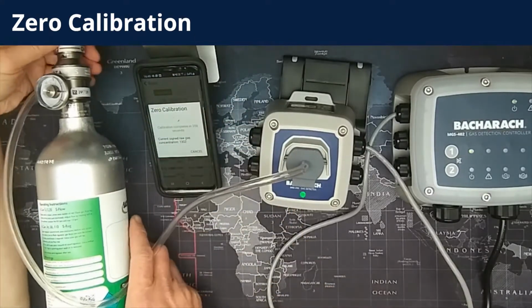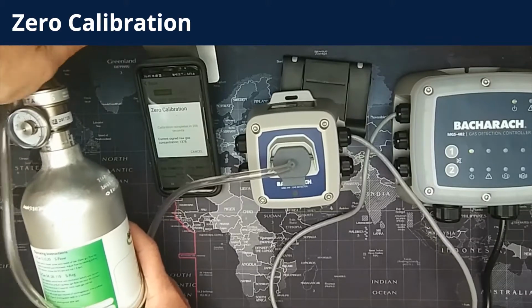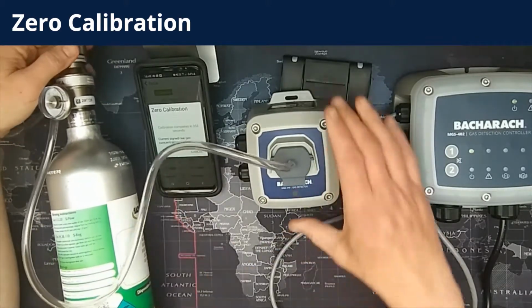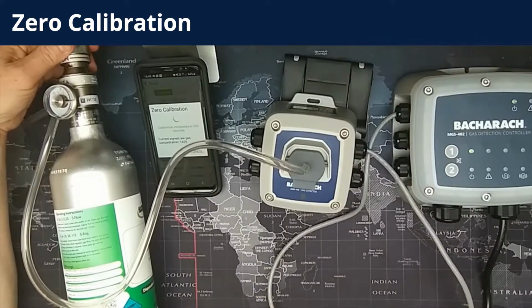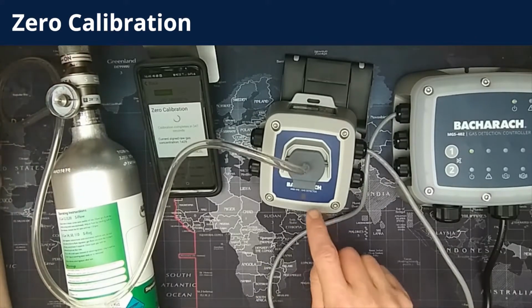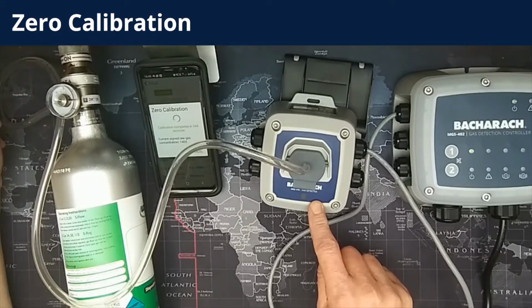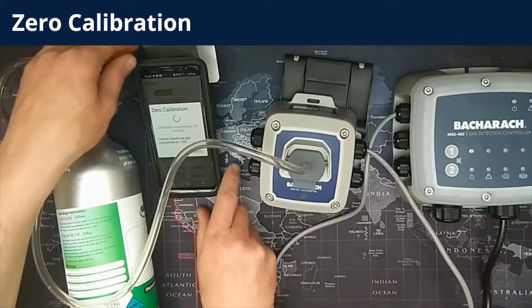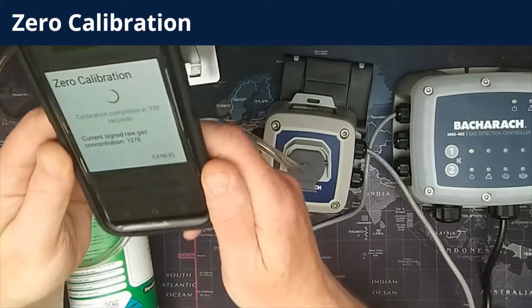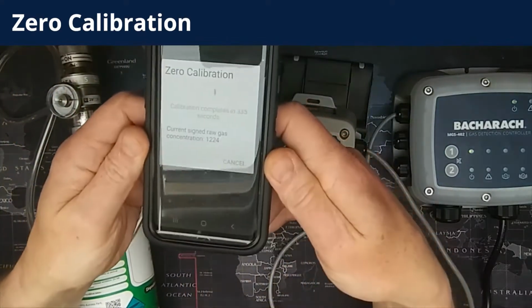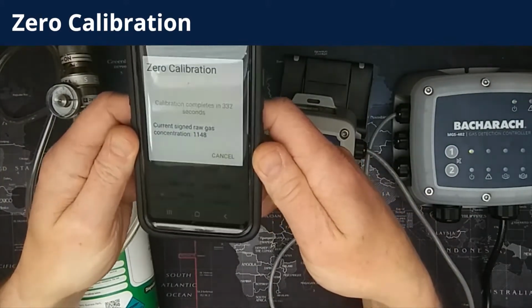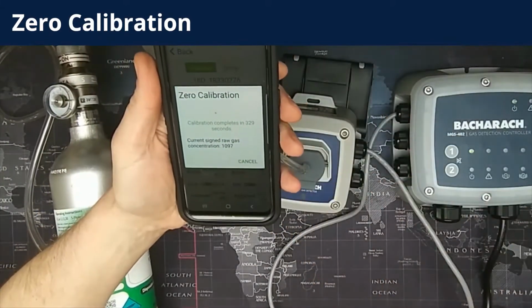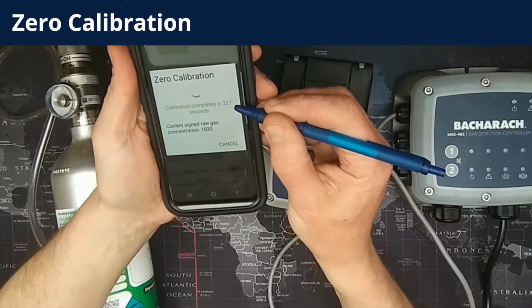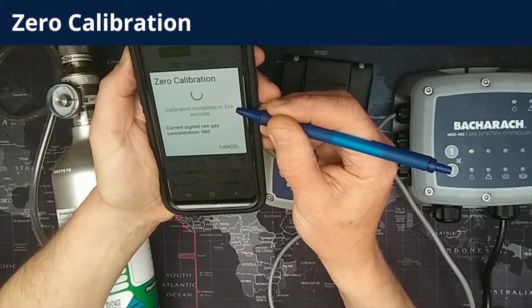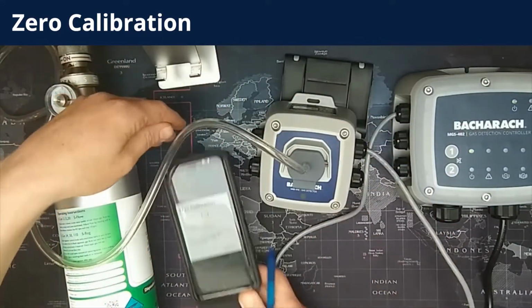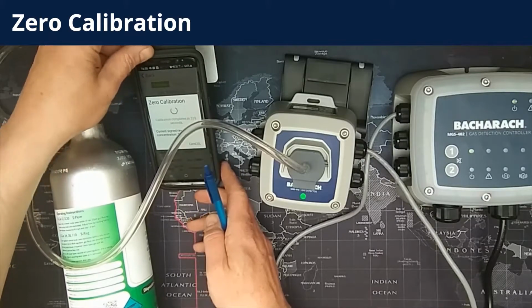That will start a countdown on the phone, which is counting down your zero calibration, and you then need to turn the regulator on to flow zero gas to the detector. The countdown on the screen shows how long the gas is needing to flow, and that will count down to 0. The LED on the device goes through a sequence of colors. That sequence is noted in the manual. You can see the countdown on the screen, and it's counting down in seconds, and the zero gas must flow to the detector for that amount of seconds. So you need to wait until that countdown reaches 0.